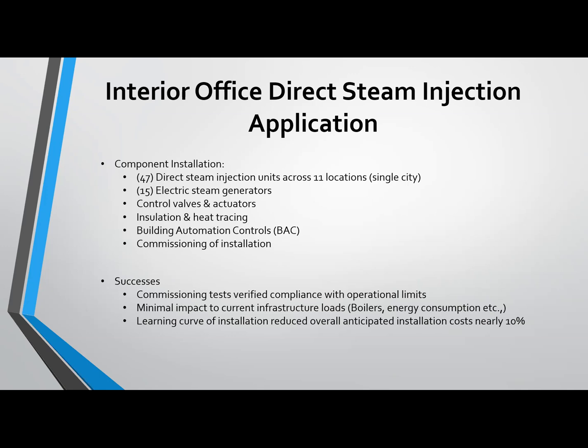Insulation and heat tracing - very technically difficult work, especially up in the spaces. For your insulation, if we're running a 1-inch steam line, we've got about 3 to 4 inches of insulation on the outside of it because it doubles that pipe. Trying to find that space, and design for that space, was a very difficult endeavor at times.